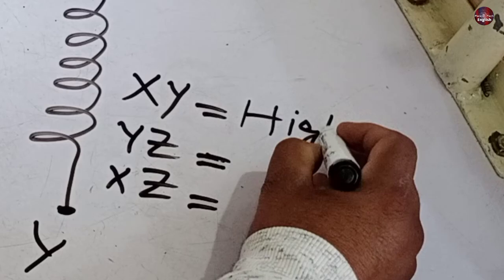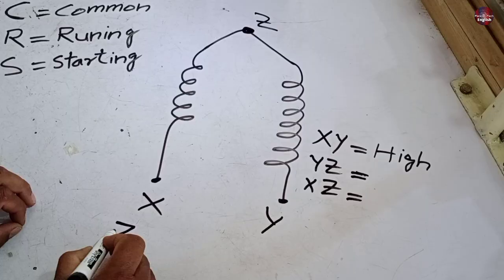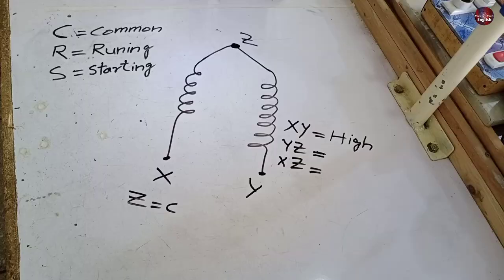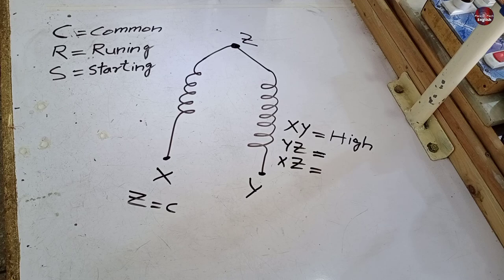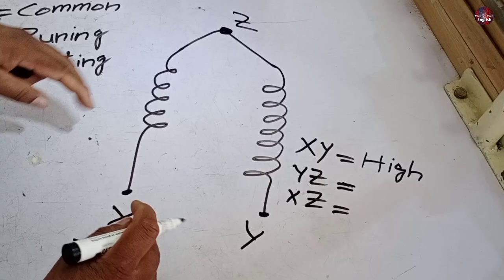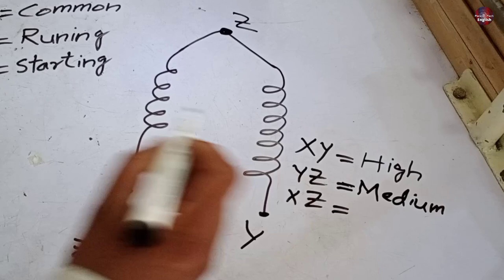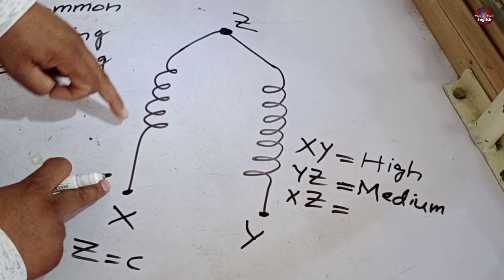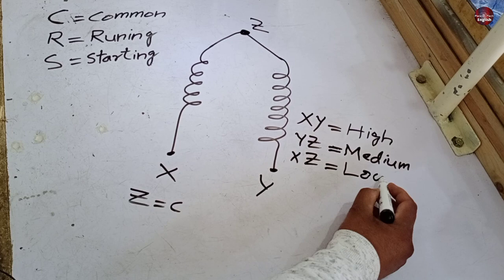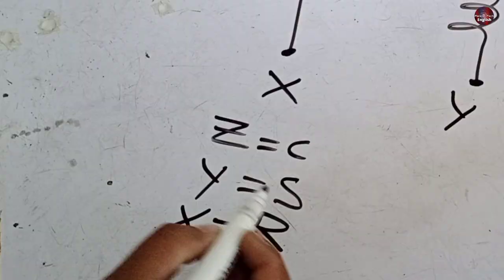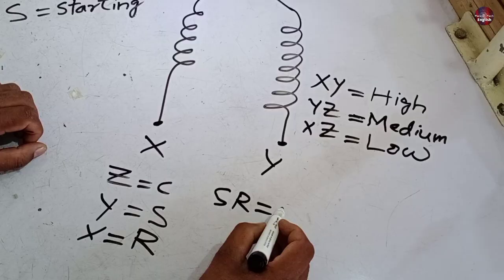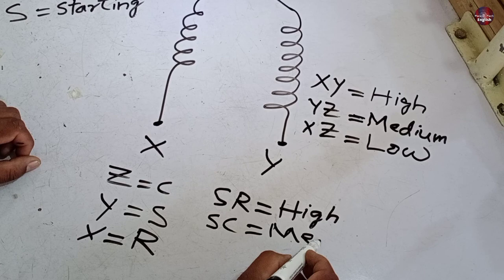Now we have a problem: whether the running winding is installed between Y and Z or the start winding is installed between X and Z. So for that, now I will suppose that Z and Y are the start winding. Always remember that the resistance reading between the starting and common will be medium value. So I am writing medium on the Y and Z. The running coil of the compressor is the X and Z, and the running and the common terminal always have the lowest resistance values. According to what I have supposed here, the Y is the start point and the X is the run point. This means the resistance value between the start and run is high, the start and common will have the medium resistance value, the run and the common have the lowest resistance values. Always remember this formula.